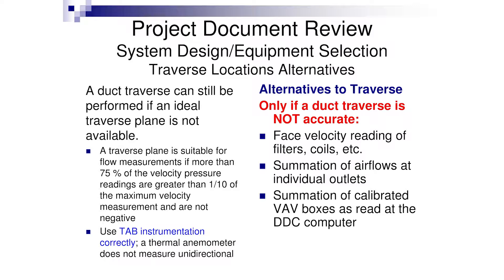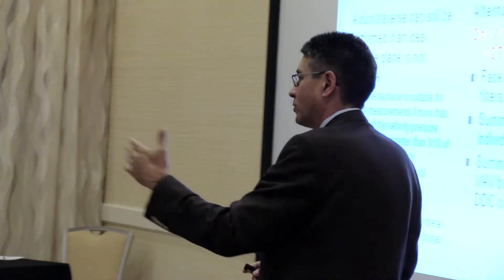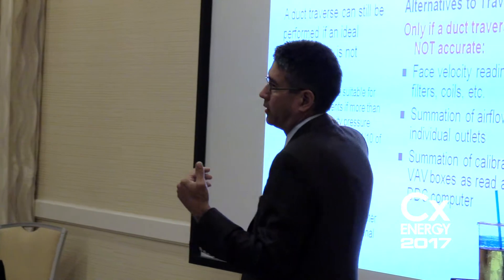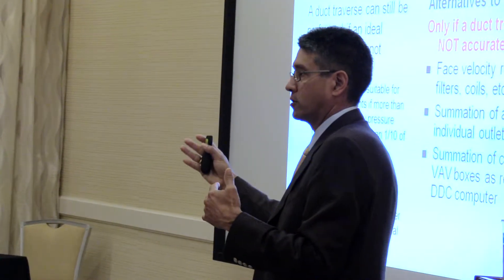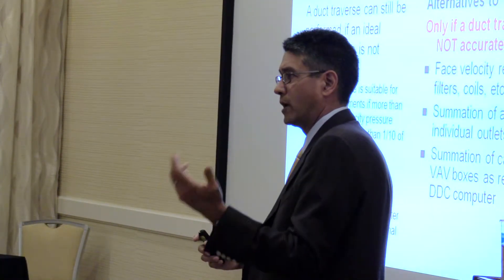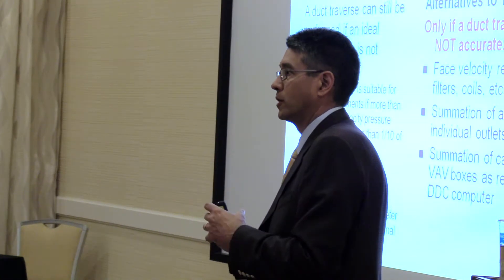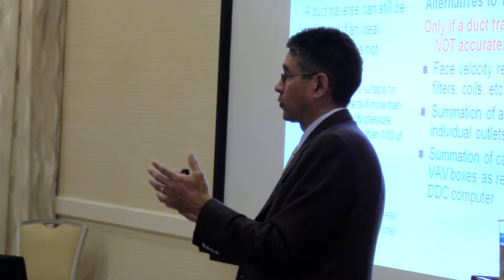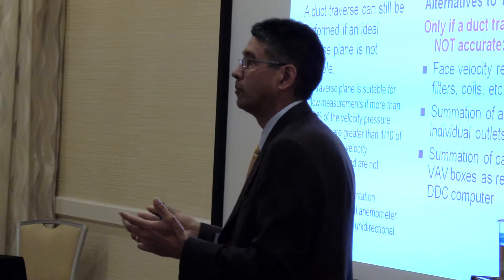On duct traverse, even if we don't have that ideal traverse plane, it's tough to say a poor traverse is better than no traverse at all, but we would still love to take one. AABC just published in their national standards that if your velocity profile is good — basically no zeros, no negatives, and within a tolerance on your velocity profile — you've got a pretty good duct traverse, even at three feet instead of six, with good laminar flow through the duct.